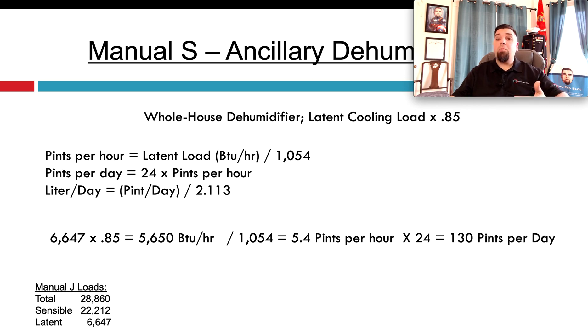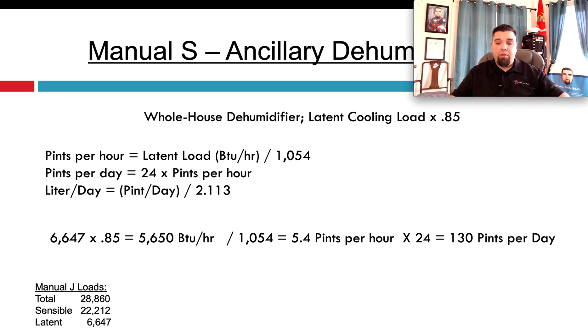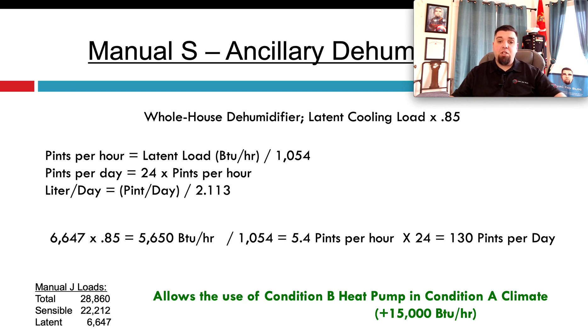We then multiply 5.4 pints per hour by 24 hours in a day, giving us 130 pints per day for this house. If you need liters per day instead, divide the pints per day value by the constant 2.113 to convert.